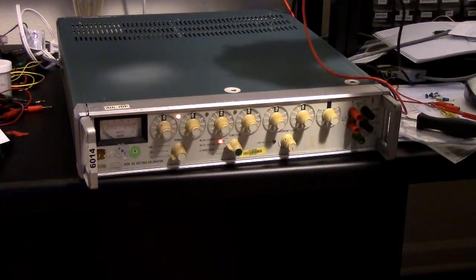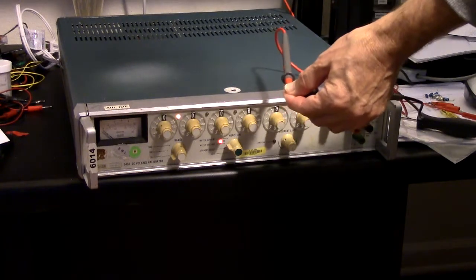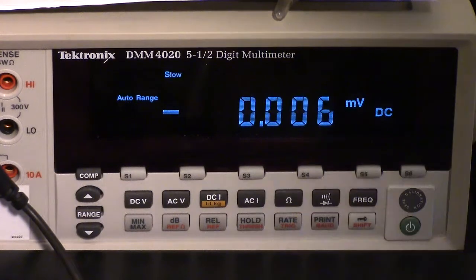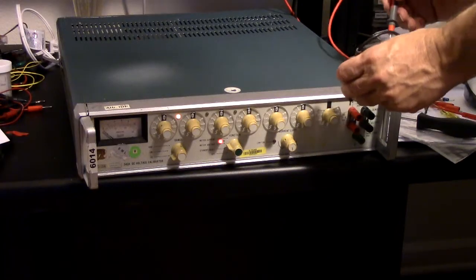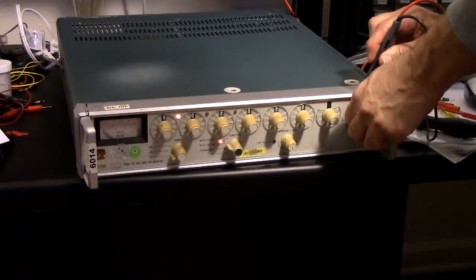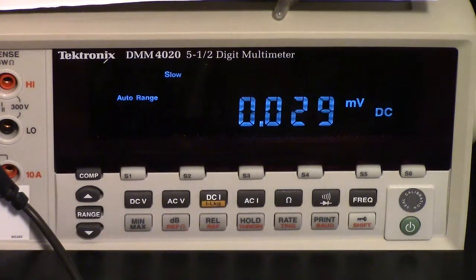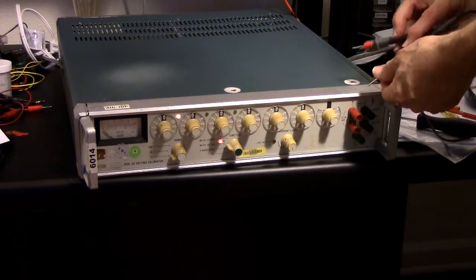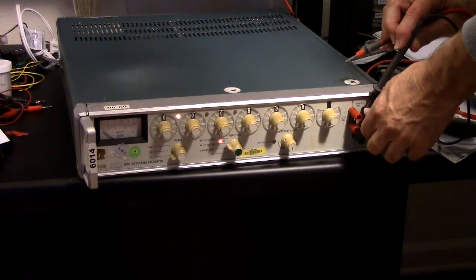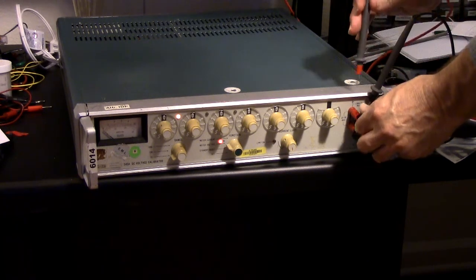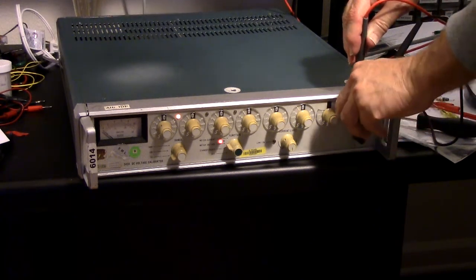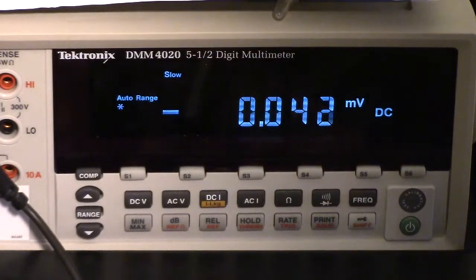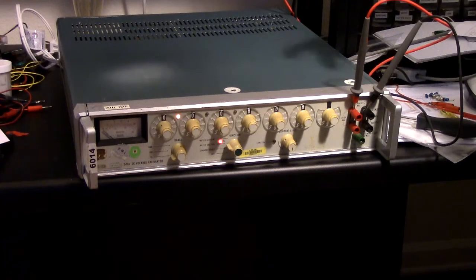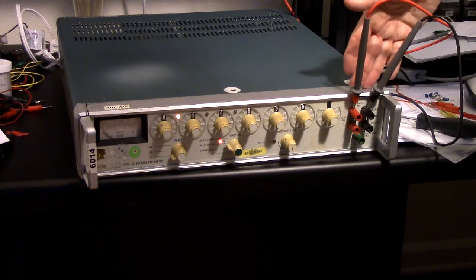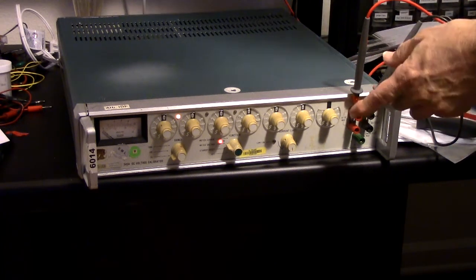If I turn this around, you know, maybe there's some offset built into the meter. I don't know. I'll short the leads together. About 6 of that is just built in to the meter. If I turn this around, so I'm showing 28 microvolts ish, versus 42, 43, or minus 43. So definitely, because I swapped the leads, the sign will change. So definitely there's something, this is not at zero output. But, so that's something maybe of concern.